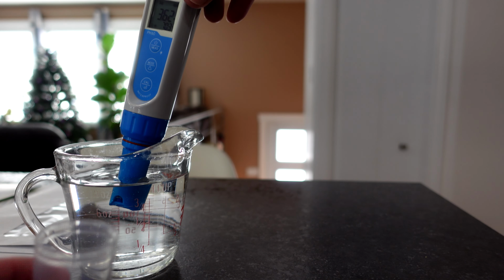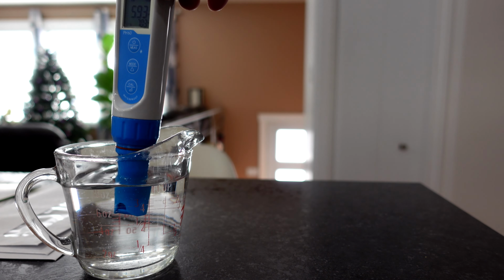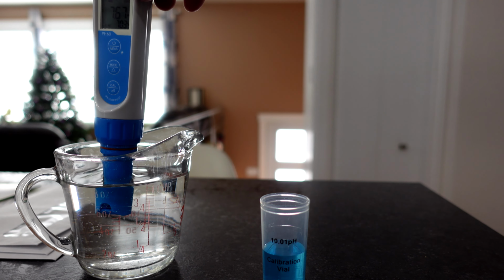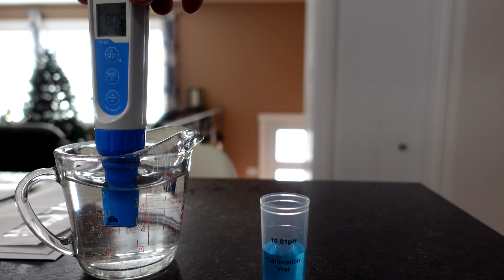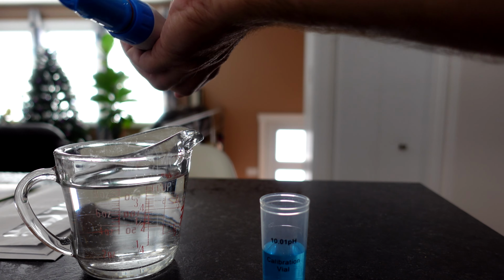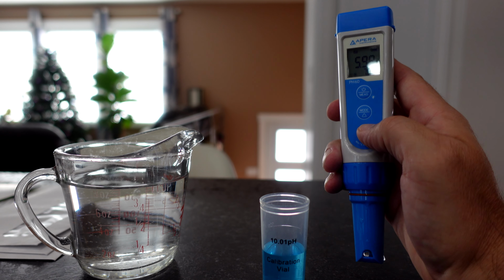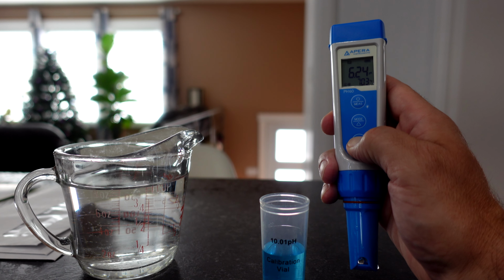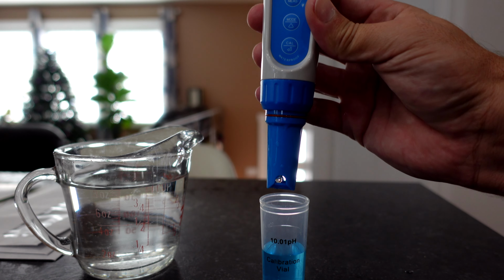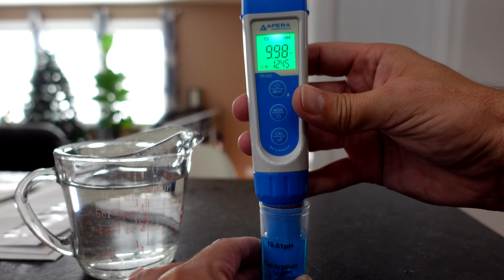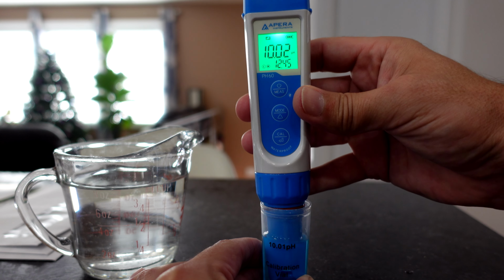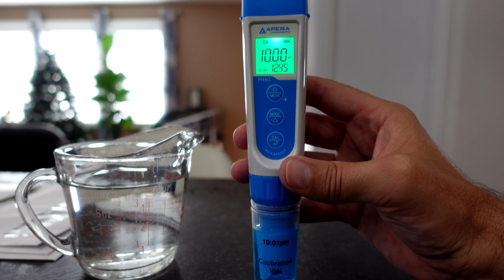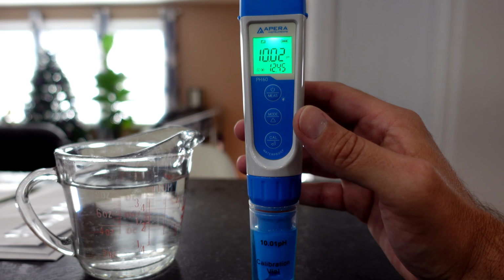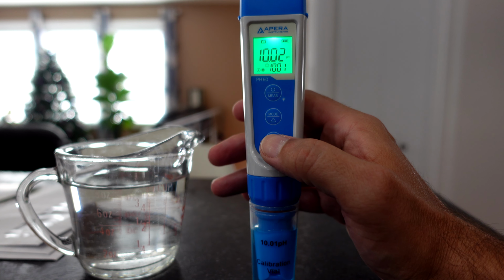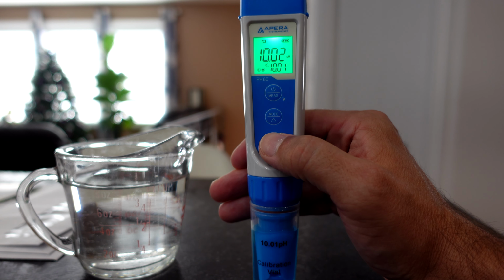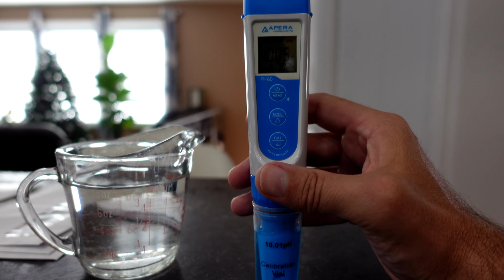Into another rinse. And my rinse solution here is RO water. If you have distilled water, that'll work too, but don't use tap water. Okay, that's rinsed. Here again, push and hold calibration. Screen turns green. And here again, into the solution. Give it a swish. And let it rest. Now we see a smiley face and 10.0. Once 10.01 stays with a smiley face and it's stable, push the calibration, and that's complete.